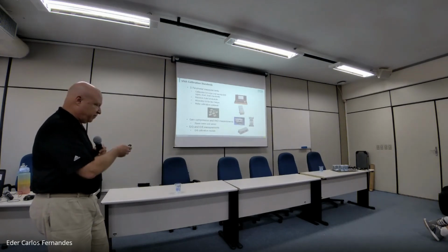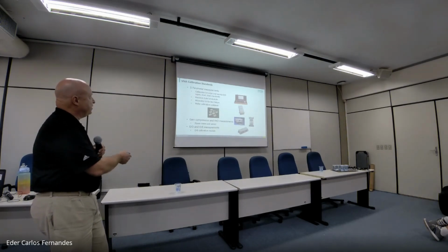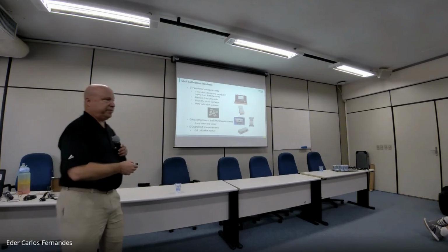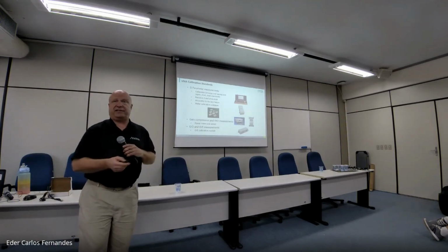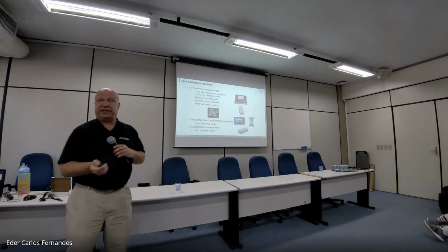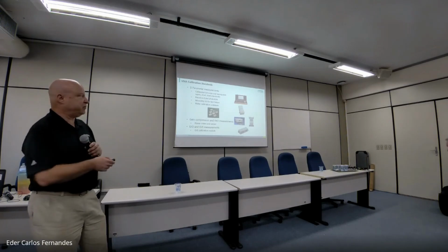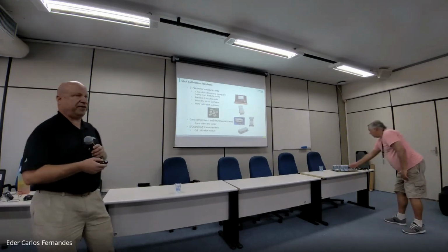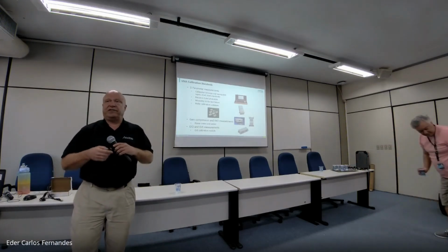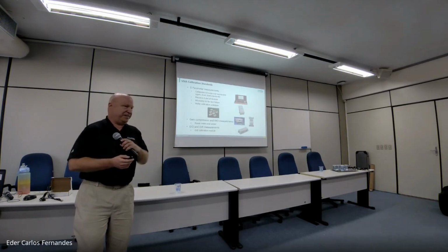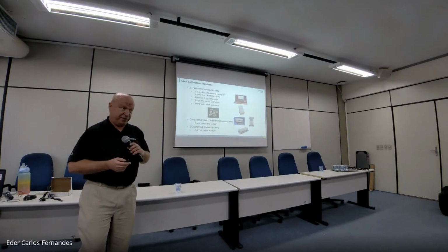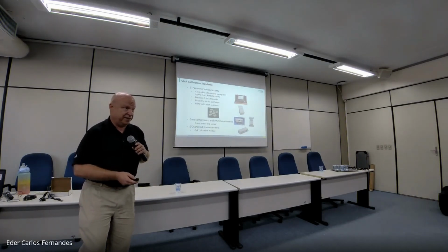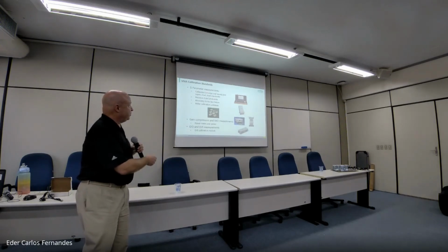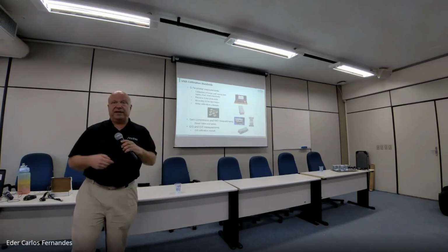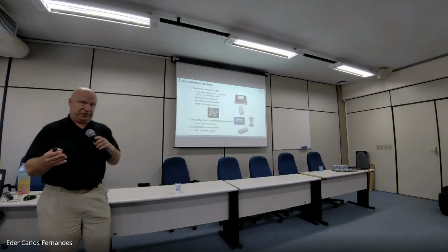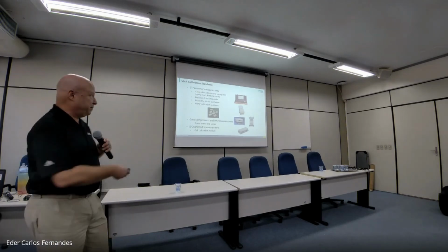So that's all for the relative or ratioed measurements that are classical with the VNA, so the S-parameter measurements. But as I mentioned, we have advanced measurements that we do now for active devices. Those require different ways of calibration, because now instead of measuring dB, as is the case with the ratioed measurements, you need to look at absolute measurements in dBm. And so I need a power meter to do that.